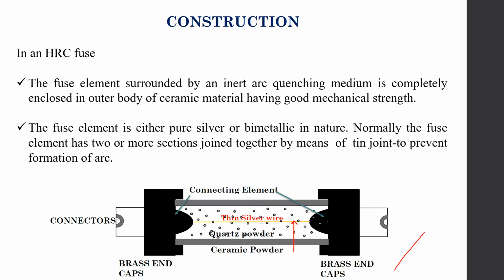The thin silver wire and the inert arc quenching medium are enclosed in an outer body of ceramic material. The ceramic material has good mechanical strength. To secure the two terminals of the fuse, brass end caps are used. With the help of connectors, we can connect this fuse in series with the circuit.